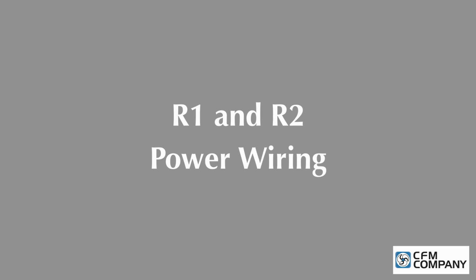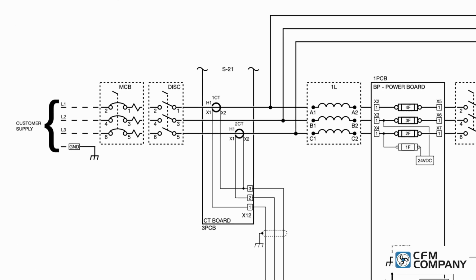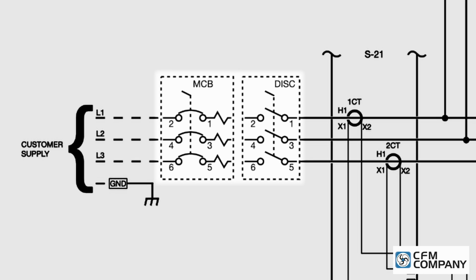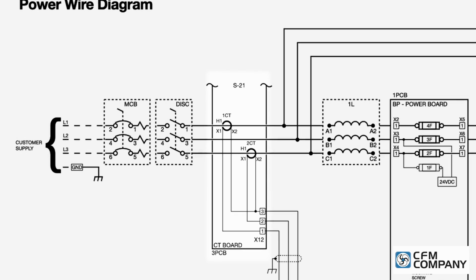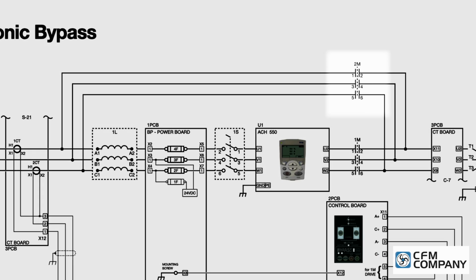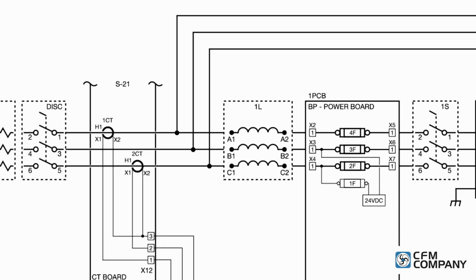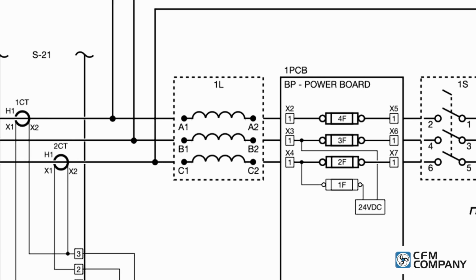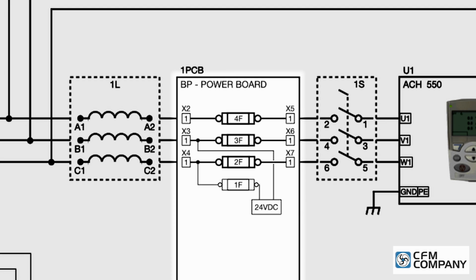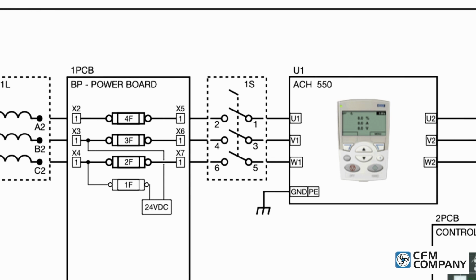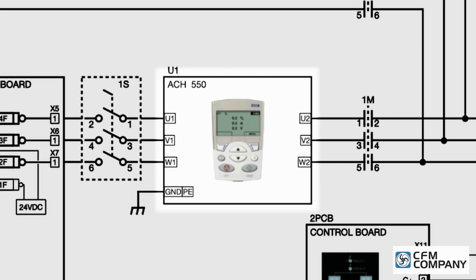Starting with frame sizes R1 and R2, the three-phase power is connected to either a main circuit breaker or a main disconnect. The power wires go through a CT board and connect to the line side of the bypass contactor, 2M. If equipped, the drive may have a line reactor. Next, the power wires connect to the bypass power board. For frame sizes R1 and R2, the drive fuses are integrated into the bypass power board. If equipped, the drive may have a drive service disconnect. The power is then connected to the drive input terminals U1, V1, and W1.